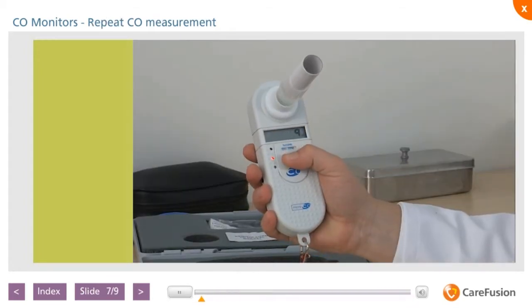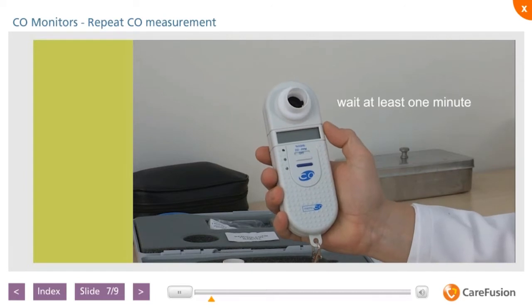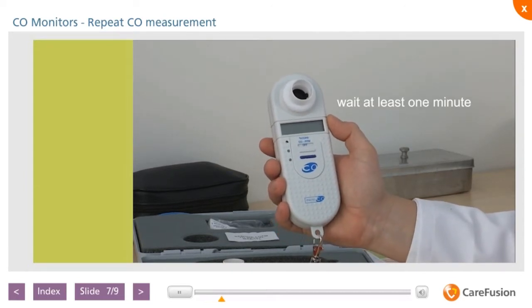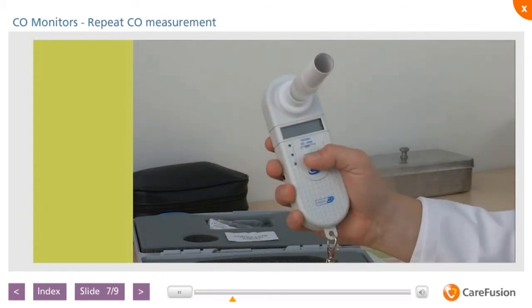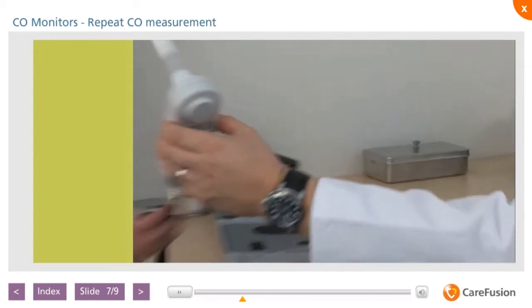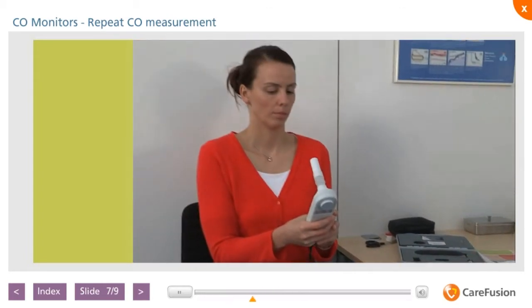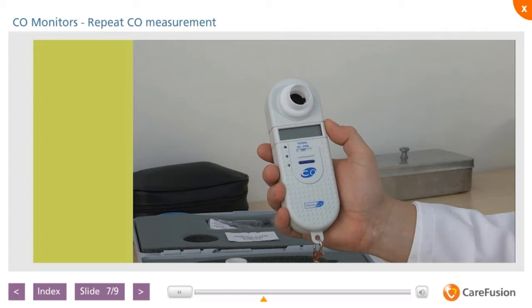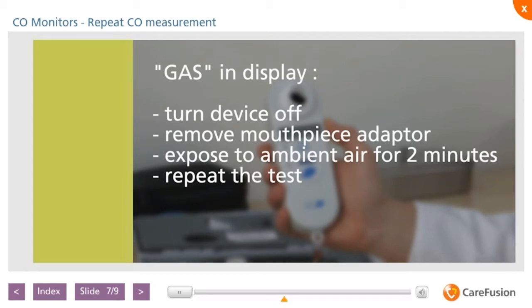To repeat a measurement, move the switch to the off position and remove the mouthpiece and adapter to allow ambient air to reach the sensor for at least 1 minute. Turn the device on and hand it back to the patient again. If the unit is switched on again too quickly after use, there may be a response to residual expired carbon monoxide from the previous test. In this case, the display will show gas. If this is displayed, then turn the unit off, remove the mouthpiece adapter, and expose to ambient air for 2 minutes before repeating the test. If this warning appears again after following the above procedure, then turn off the unit and leave the sensor exposed to ambient air for a further 3 minutes.